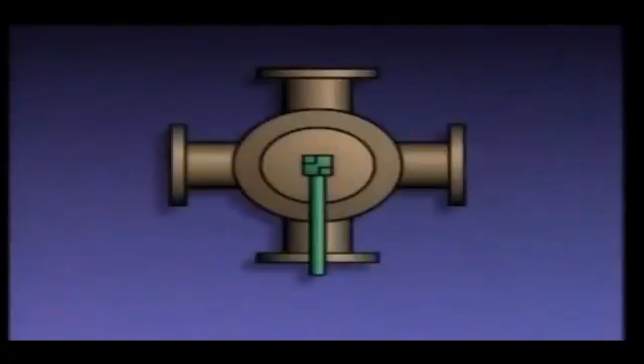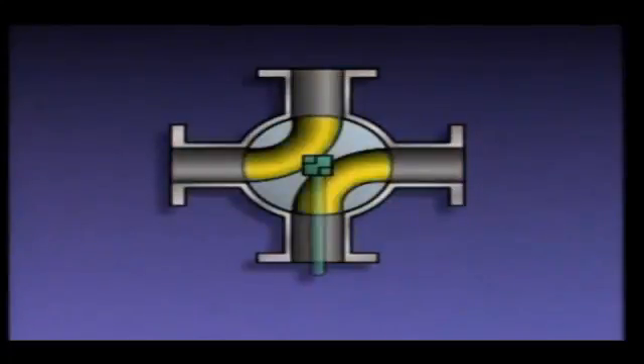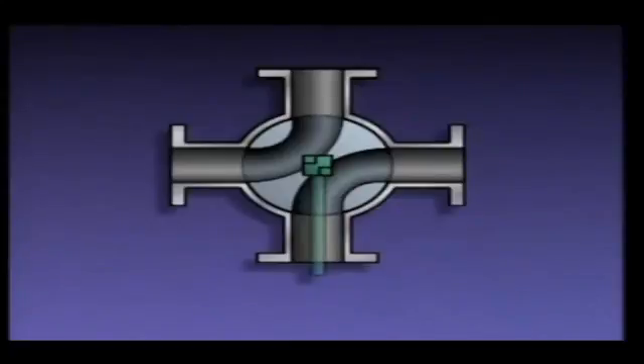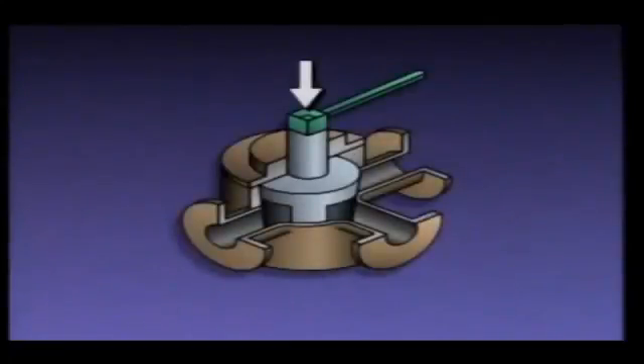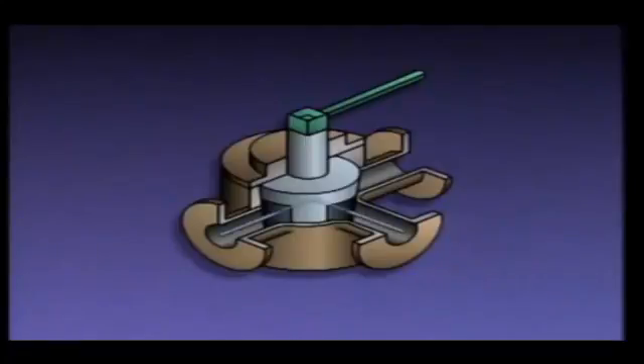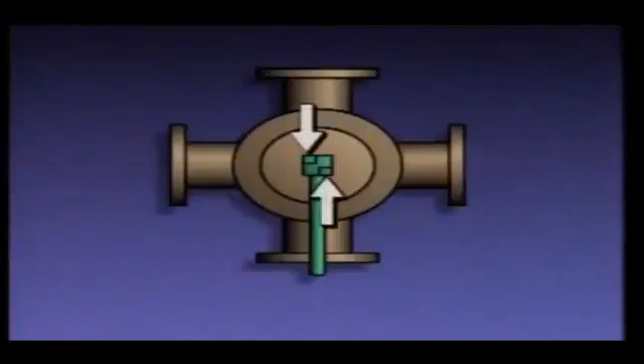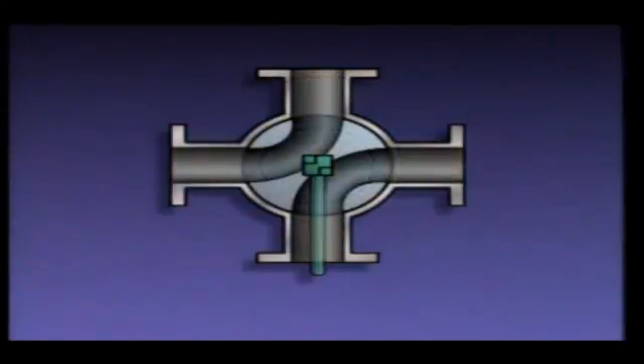Some multi-port plug valves have more than one L-shaped opening. Here is an example of a plug valve with two L-shaped openings, called a four-way valve, commonly used to change flow through a piping system. Multi-port plug valves usually have L-shaped markings on their handles to indicate valve position. Three-way plug valves usually have one L and four-way plug valves usually have two. By comparing the L positions to the piping, the direction of flow can be determined.